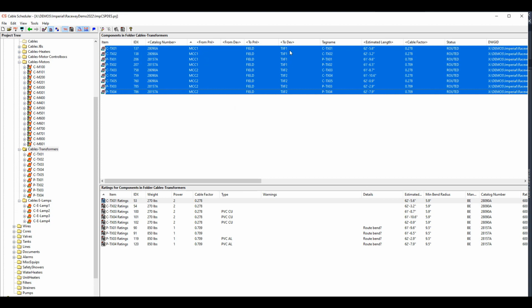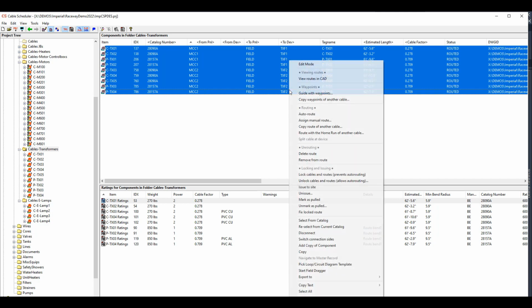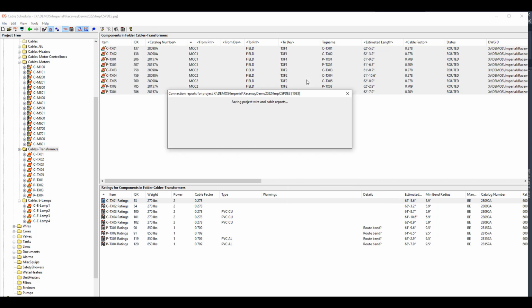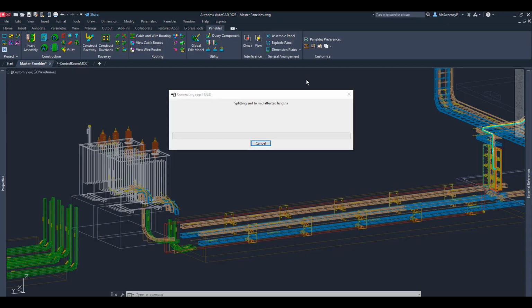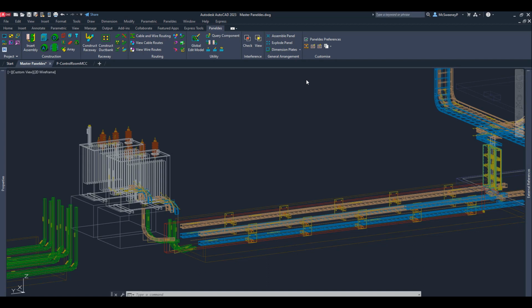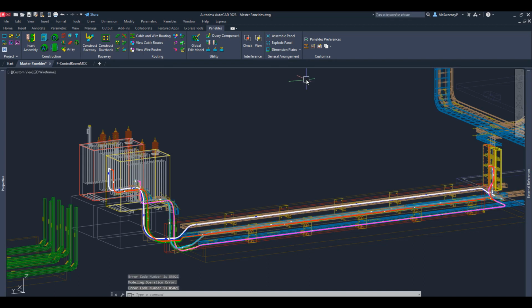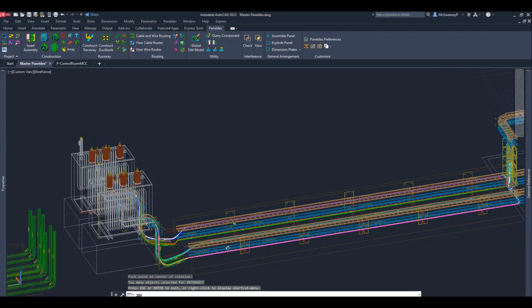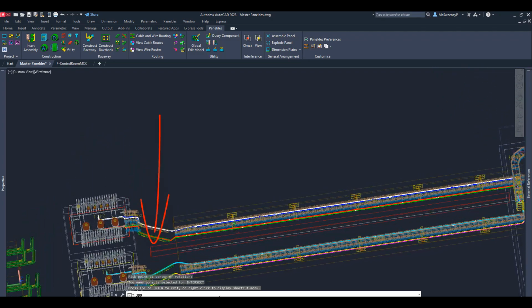In this case, an area or accessory can be marked as an obstruction. Cables in a Paneldes model can route anywhere where raceway is provided, but sometimes trays can get too close to the other trays, allowing undesirable routes to develop. GIS substations and offshore projects are notorious for this. We can stop these close raceways from sharing cables with an obstruction. In my model, I do not want any of the raceway used for the east transformer to be used to carry cables from the west transformer, and vice versa. I have placed a red obstruction wall along the centre of my trench to stop the sharing of the east-west raceway.